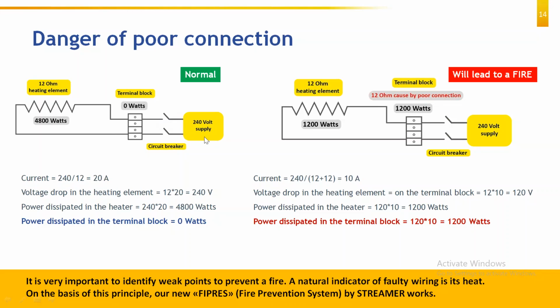Now we will take an example when there is some abnormality in the system. The same circuit having 240 volt with a 12 ohm heater in the line, but in this scenario we have 12 ohm of poor connection at the terminal block. We are considering a poor connection which is causing 12 ohm resistance at the terminal block. Now we will try to analyze what will happen in this scenario. In this circuit we have a 240 volt power supply, then a 12 ohm resistance at the terminal block because of the loose connection, then a 12 ohm resistance because of the heater.